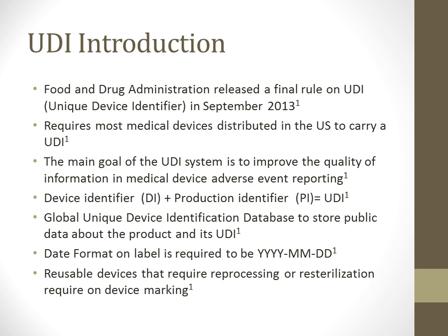There's another part of UDI that's going to be required called the Global Unique Device Identification Database, or the GUDID. That's what my company is calling it for its acronym. Its goal is to store public information about your medical device data and its associated UDI. There's a bunch of data elements around this database, around 60, that include regulatory information, labeling data, your sterilization method, measurements of the device, and various other information that all tie around this UDI for your particular device.